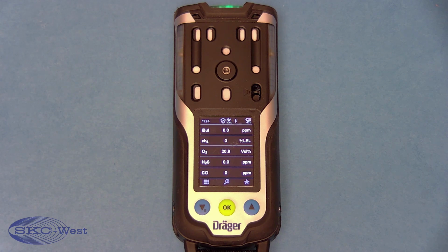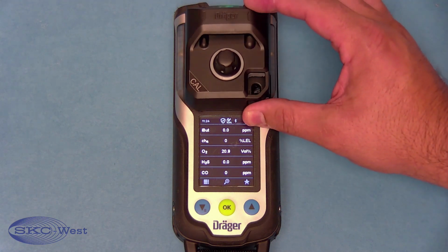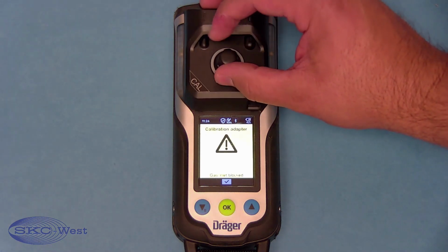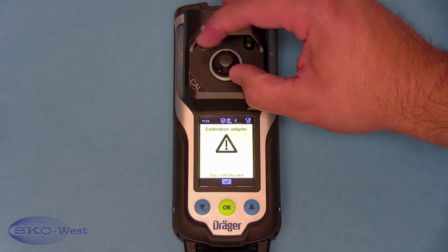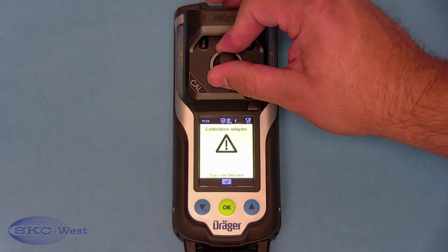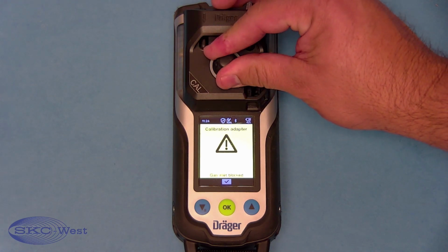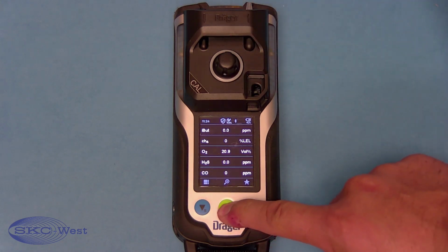For the piece of tubing that you use to plug into the calibration adapter, be sure you put it on the left side of the calibration adapter that has the arrow pointing down into the instrument. To insert your monitor onto the calibration adapter, you just screw the calibration adapter onto the front.